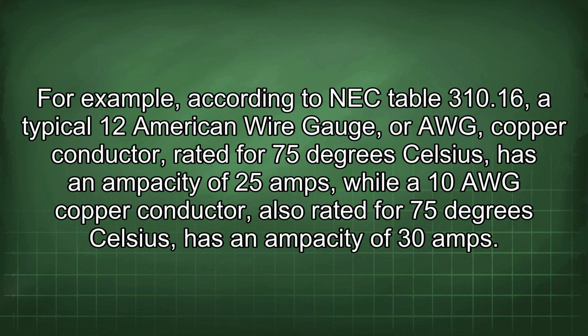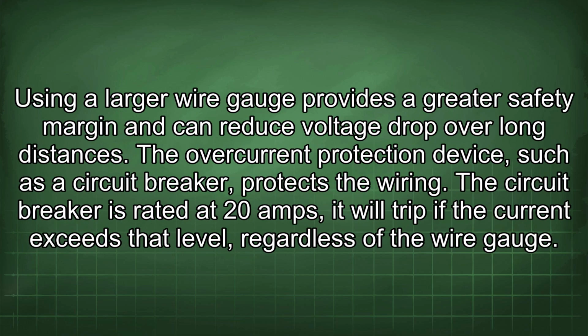For example, according to NEC Table 310.16, a typical 12 American wire gauge, or AWG, copper conductor, rated for 75 degrees Celsius, has an ampacity of 25 amps, while a 10 AWG copper conductor, also rated for 75 degrees Celsius, has an ampacity of 30 amps. Using a larger wire gauge provides a greater safety margin and can reduce voltage drop over long distances.